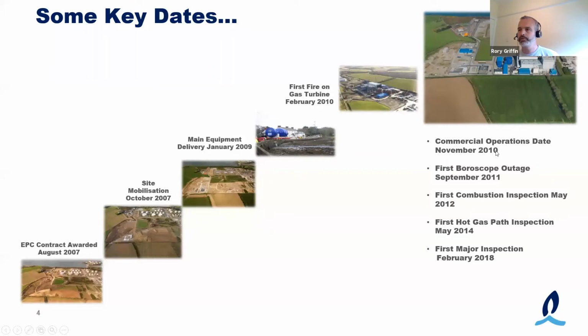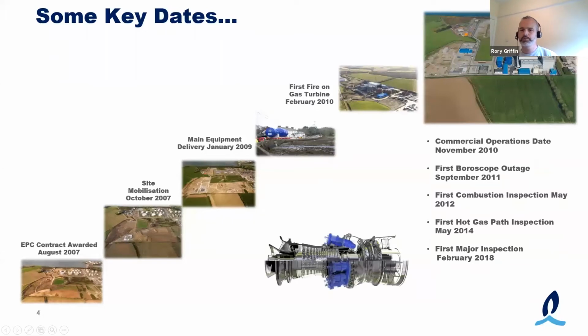So I have some other dates here, just some of the milestones in terms of the maintenance inspections on the unit. So in September 2011, it did its first borescope inspection. So this is where you get a camera. Now when I say camera, it looks more like an optic fiber camera, but it's on a long rope for want of a better description. And you can remove plugs in the machine and get the camera in, you can get a look at the blades. So really what you're doing is having a good look in around the unit before your next larger outage.